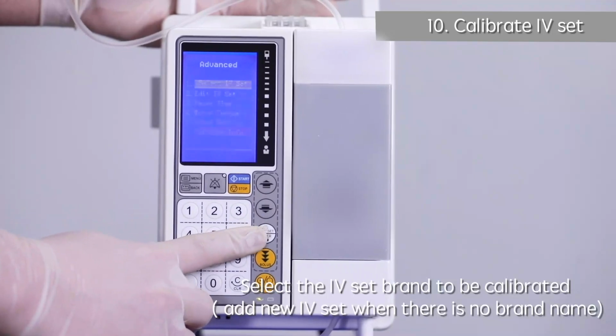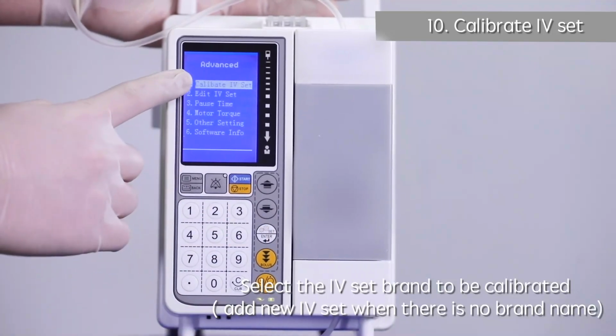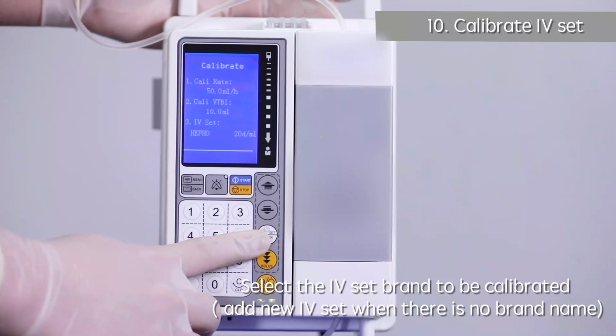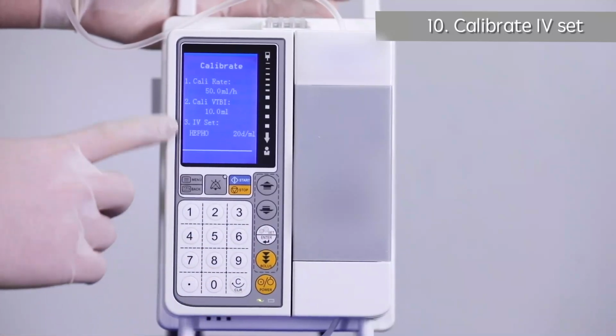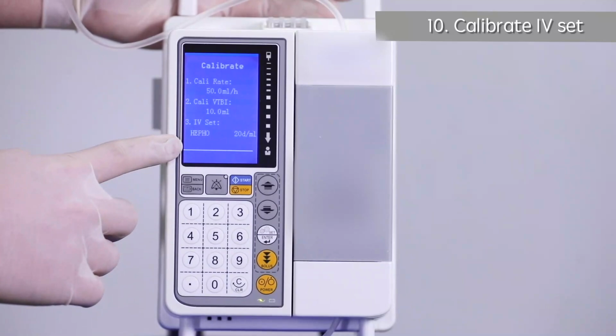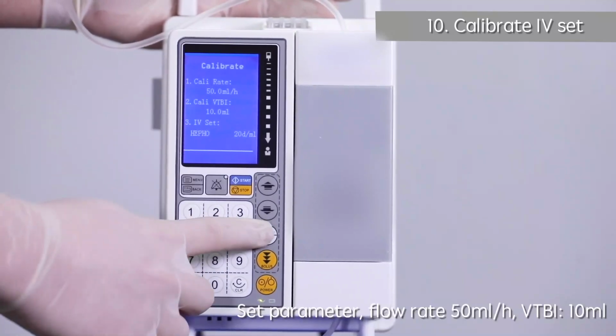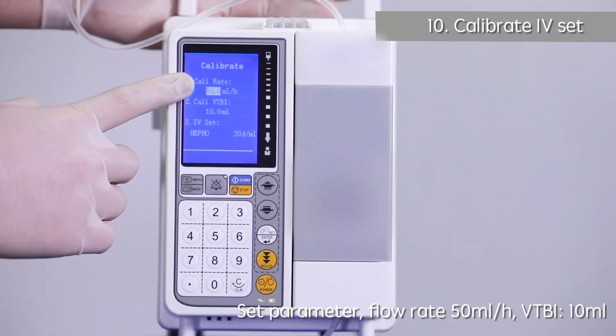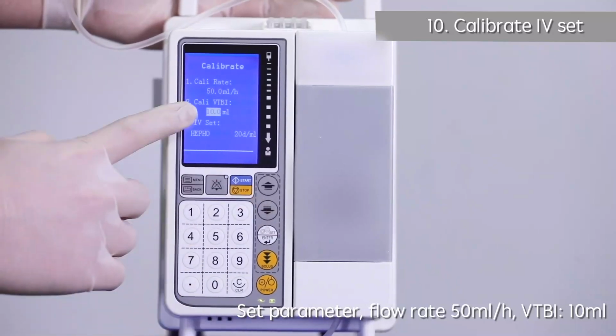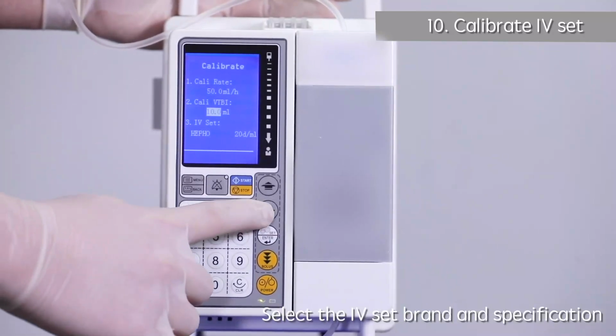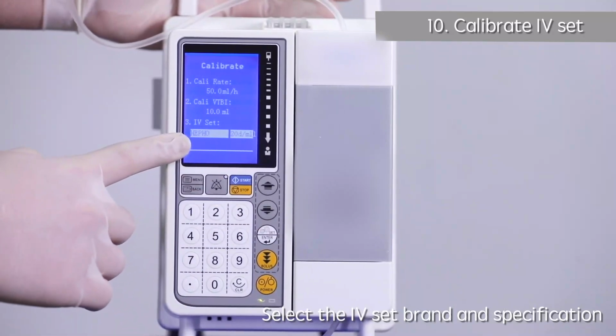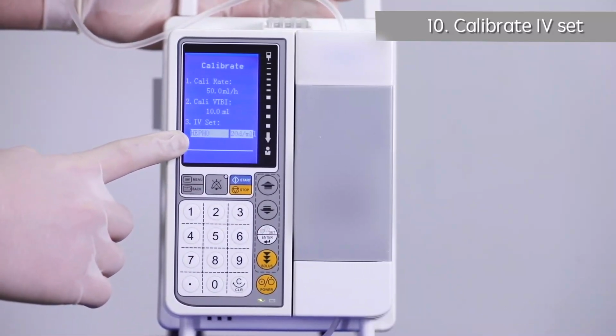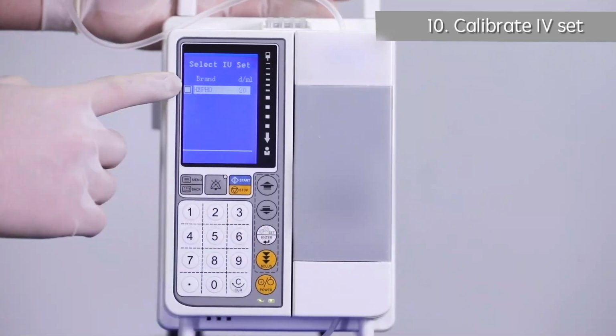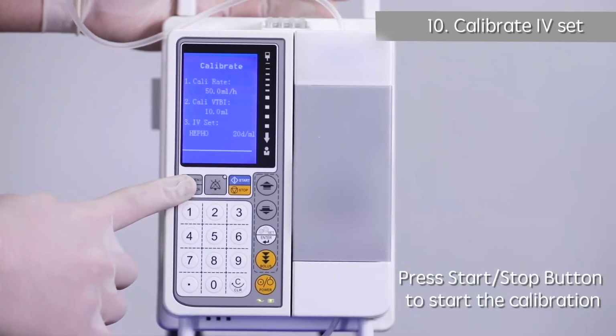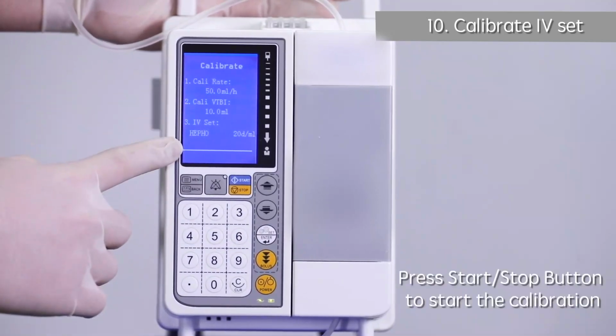Select the IV set brand to be calibrated. Add a new IV set when there is no brand name. Set parameter: flow rate 50 ml per hour, VTBI 10 ml. Select the IV set brand and specification. Press Start/Stop button to start the calibration.